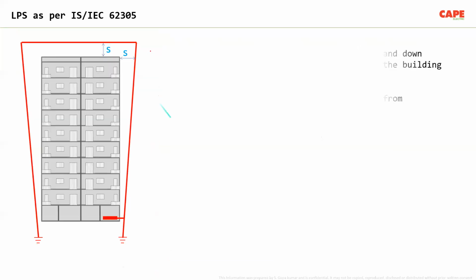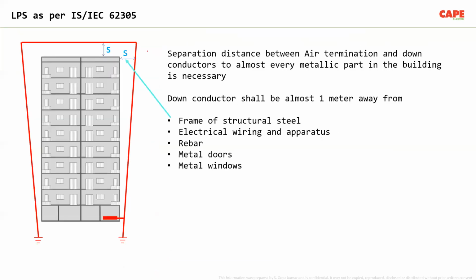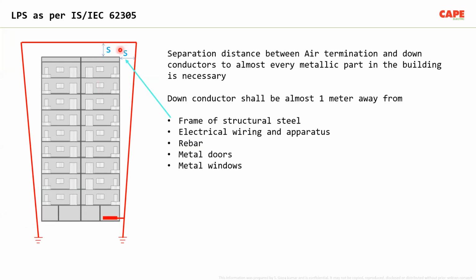So how do we handle that? There are calculations given in the standard. We have to calculate the separation distance, and basically all these down conductors must be kept away from the building. So if, for example, the separation distance is 1 meter, the down conductor must be kept 1 meter away from the building. This is a mandatory requirement.